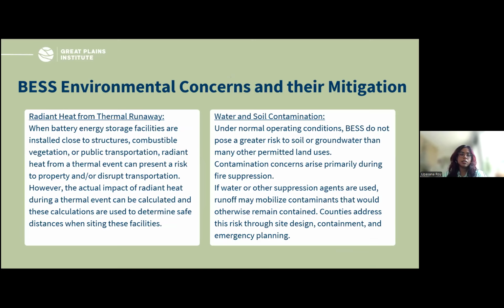The risk we're talking about is usually thermal runaway. Battery energy storage systems are essentially racks of cells. Usually there might be a little electrochemical issue within one pack, and that will go on to light up another pack, and then another, and it goes on. That's why it ends up starting a cascading effect, which is why it's called thermal runaway. But it's not as scary as it sounds—it usually gets contained within the system once it starts.